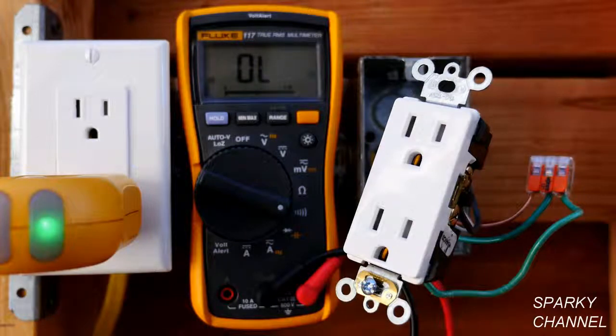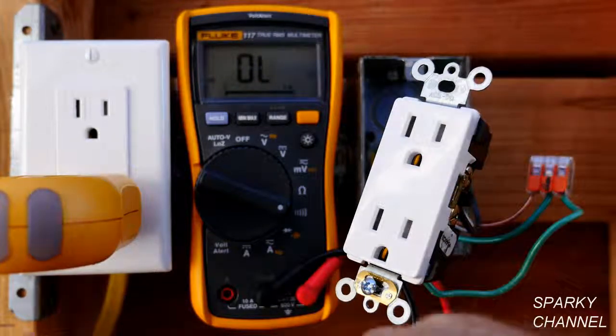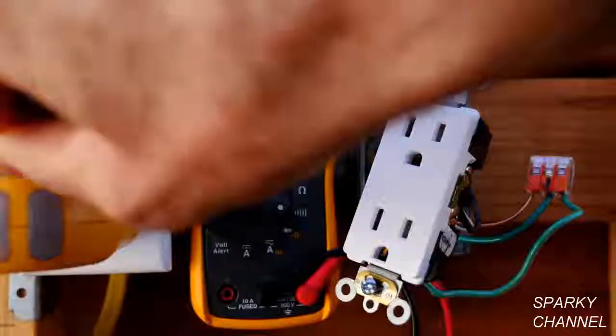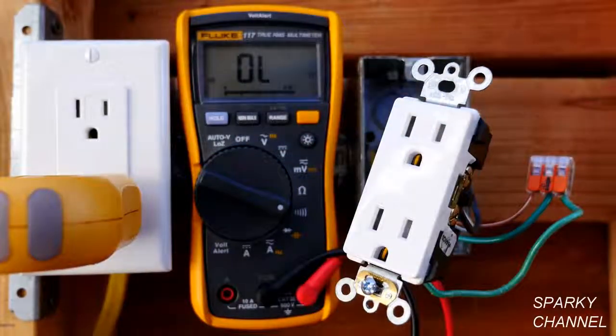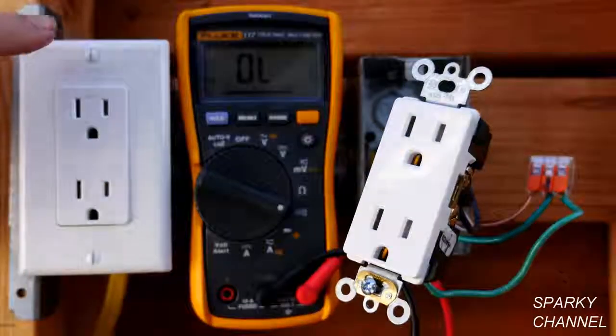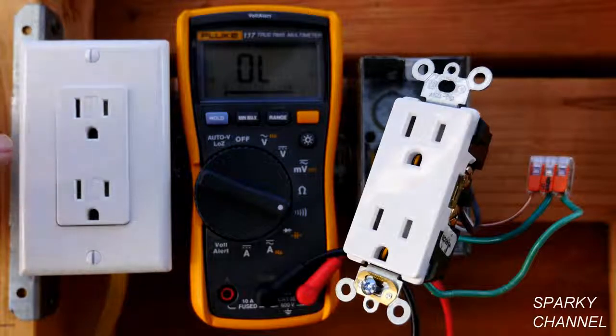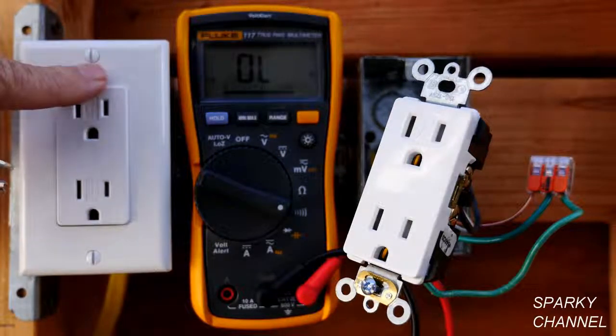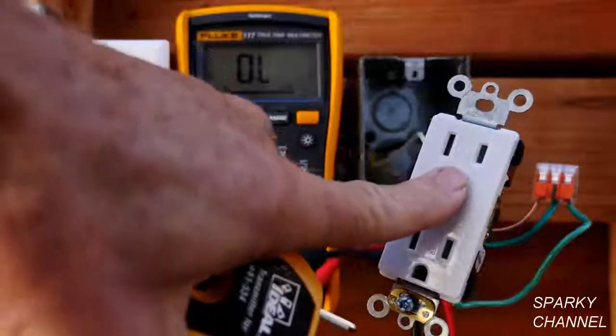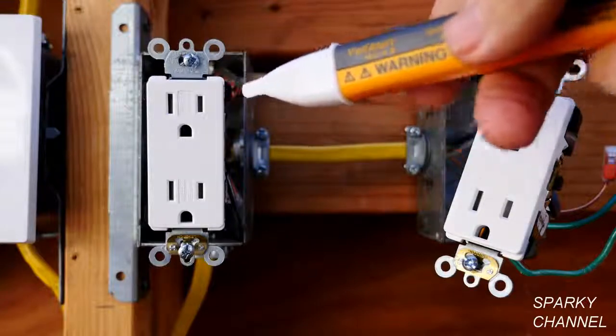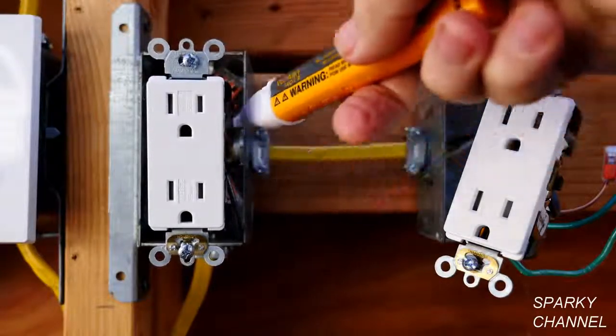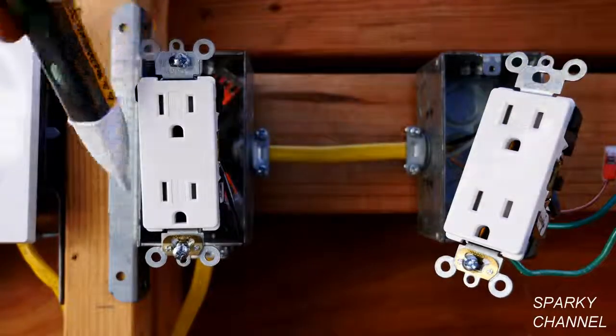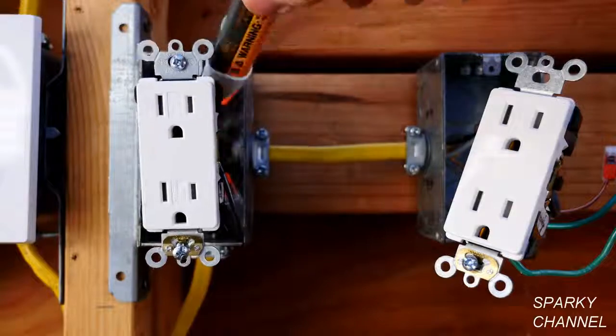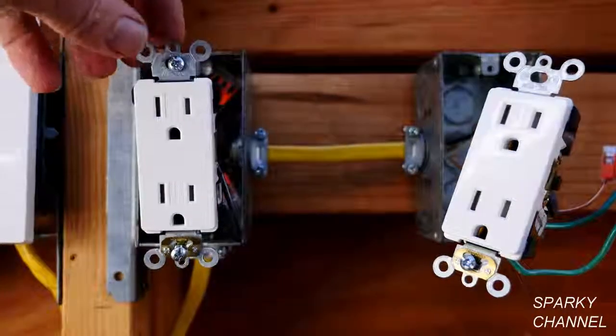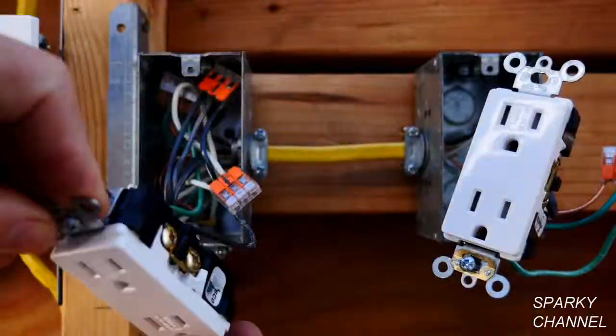Now I'm going to turn the circuit breaker off. I've turned the circuit breaker back off, and the outlet detector says there's no electricity in the box, and I'm going to use my voltage detector, and it agrees that the circuit breaker is off. So now I'm going to go ahead and take off the wall plate and remove the receptacle, and we're especially going to be looking for the neutral connection that brings the neutral wire over to this receptacle. I've removed the wall plate and taken out the outlet, and now I'm going to use my voltage detector as a double check to make sure that there is no hot wire at all in this box. Okay, so let's pull this out and examine everything.